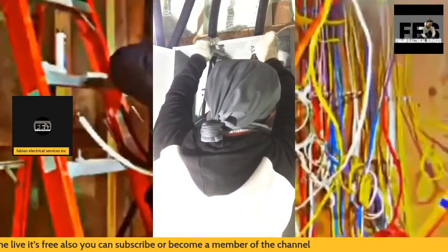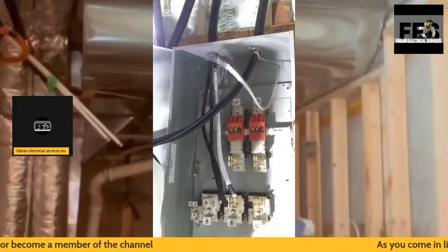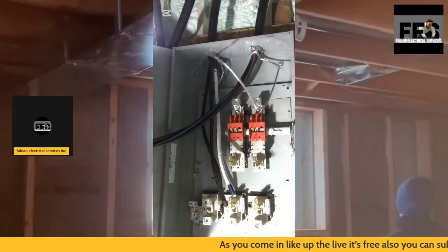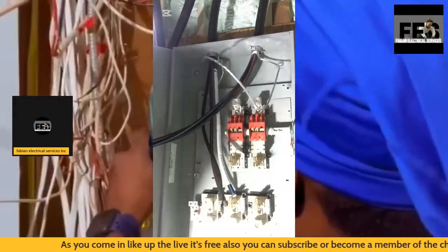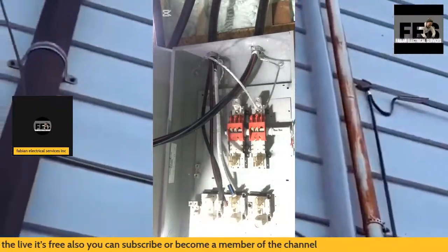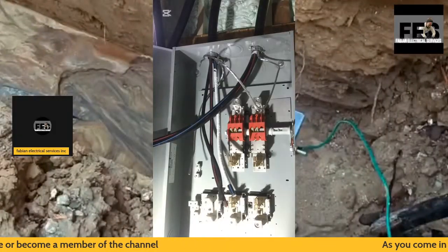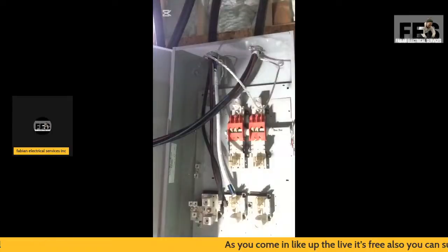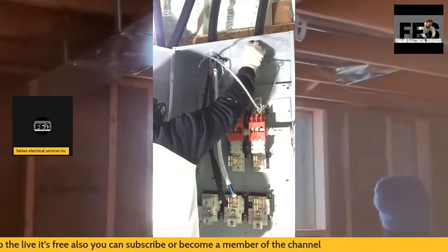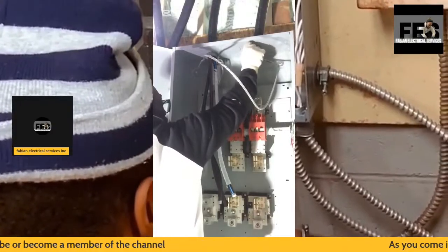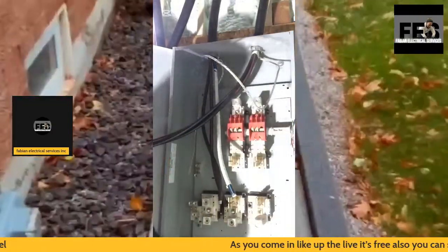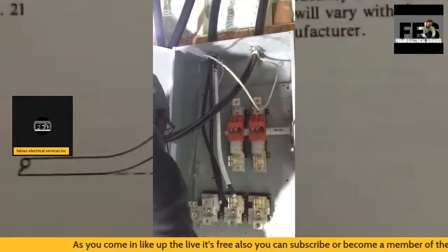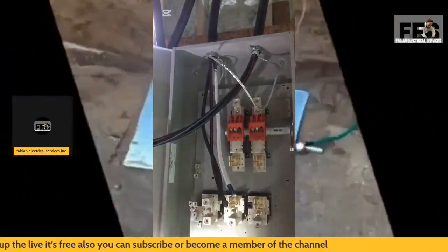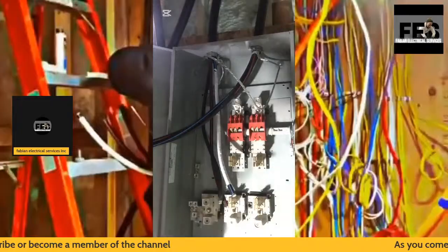Also, you're going to see I have my phasing tape on my cable. The reason is this cable does not come with an identified neutral, and in the code book it states that your incoming neutral has to be identified. There is a code compliance rule that states that for a particular size of cable we must identify it. So this is what I am doing here, identifying my conductors with the white tape. It's always best to keep your line and loads separated. Never have them touching each other. It is a code compliance rule that states that your main feed coming in is not supposed to come in contact with your load side that's going out. So for this reason, you're going to see the installation.